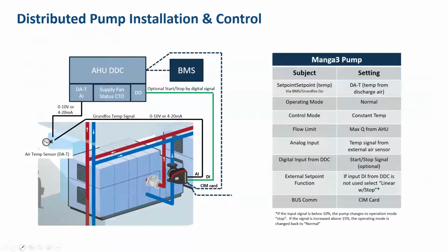All right, if we look in more detail at the options that we have for setup and control, the first one is what we sort of talked about here, is that we're going to take that 0 to 10 signal directly from that sensor and operate the pump accordingly. It's about the most simple and quickest reacting option we have. The next option would be through the air handler's DDC.